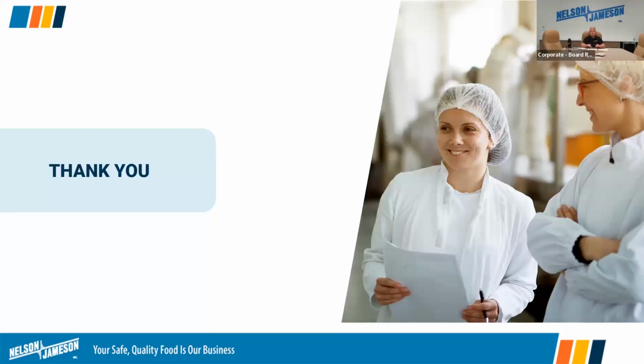We got a few questions from Amanda here. First question is, are there certified explosion-proof units available for different budgets? Yes, there are. Depending upon what your dust hazard analysis dictates, there are explosion-proof units used in applications or environments where there is combustible dust in the air and you are still housekeeping. There are Class 2 Division 2 or combustible dust safe vacuums. Once the dust is settled and your operators come in to conduct the housekeeping, you have that option available. Or there are compressed air vacuums, which do away with any sparking motor, so it limits that ignition source. The next question is, can I have more than one person using a vacuum at a time?